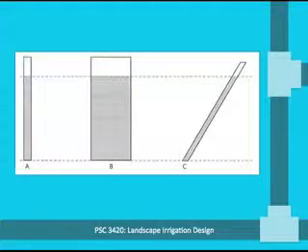So what this means in terms of irrigation systems is that when sprinklers or drip emitters are at different heights, or when irrigation pipes follow the contour of the land, there will be a difference of 0.433 psi for every foot of elevation change, and that will be positive or negative depending on whether the change is upward or downward.